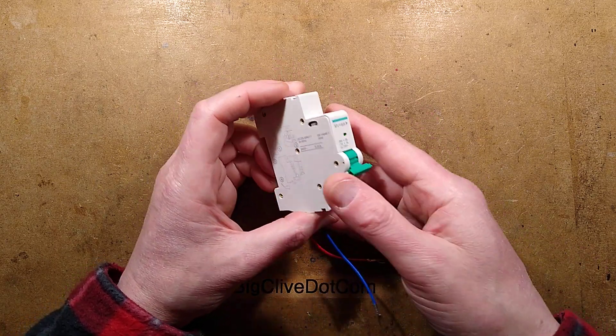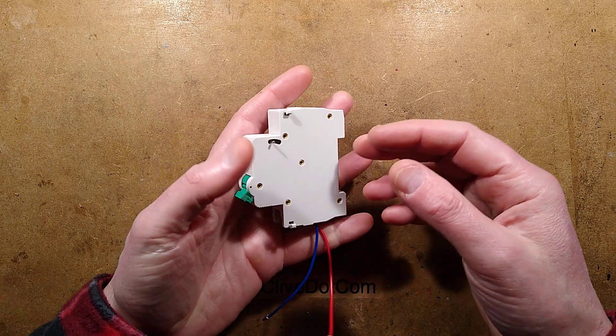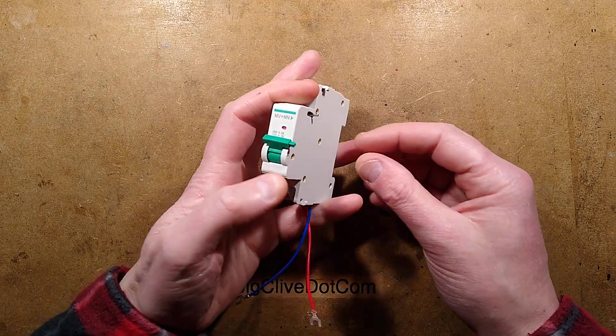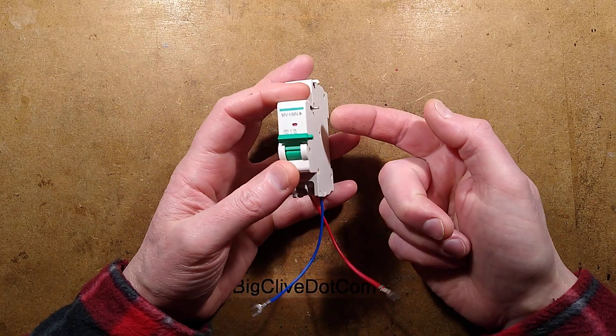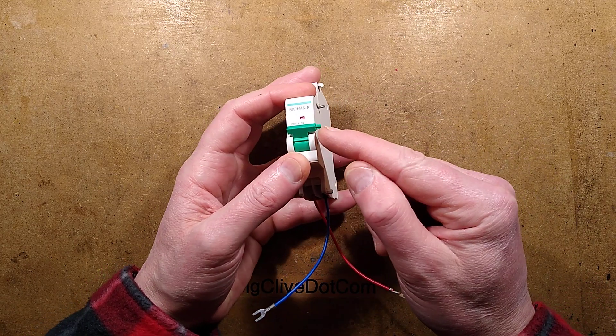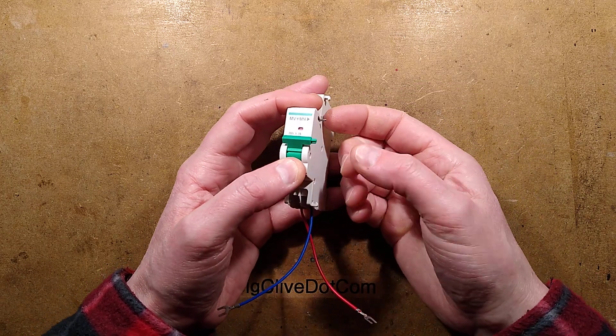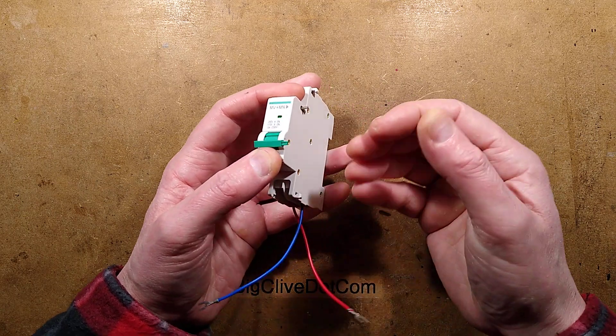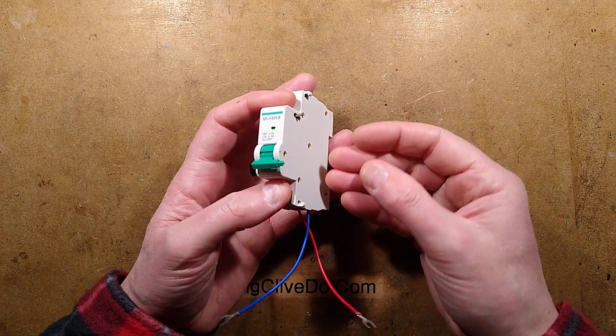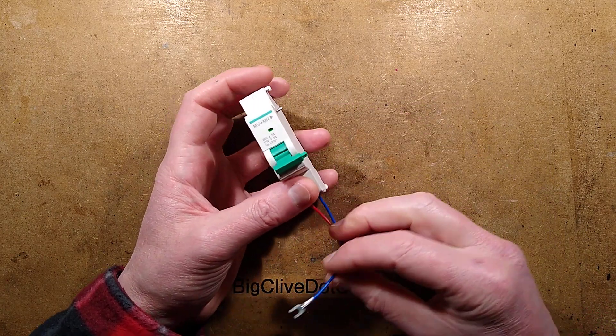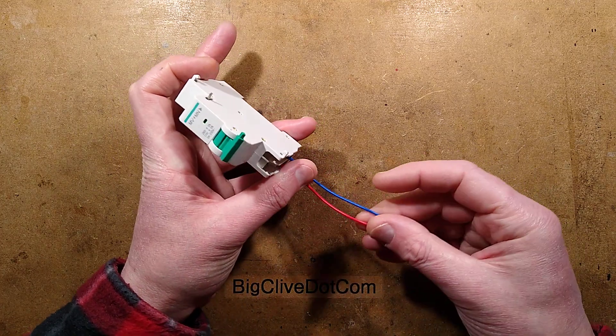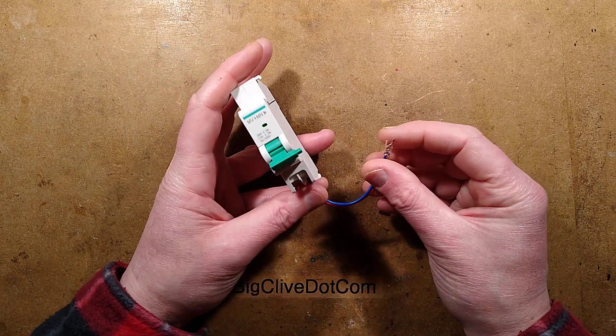This thing, I've been trying to guess what's inside it. It's very very light. Obviously you set it manually and it's got this pin that interlocks to the breaker at the side and this interlocks to the lever at the side. When it trips, all it has to do with the magnet is just pulse that once and it trips. I've already measured the resistance across this, it seems to be open circuit-ish.